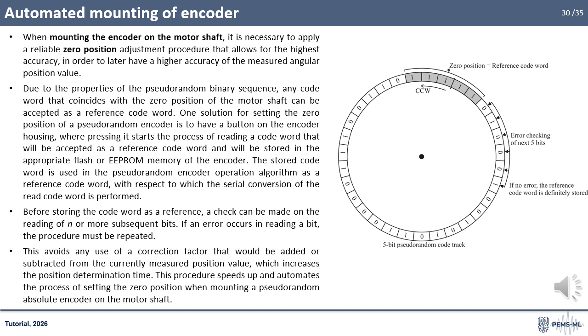One solution for setting the zero position of a pseudorandom encoder is to have a button on the encoder housing, where pressing it starts the process of reading a code word that will be accepted as a reference code word and will be stored in the appropriate flash or EEPROM memory of the encoder. The stored code word is used in the pseudorandom encoder operation algorithm as a reference code word, with respect to which the serial conversion of the read code word is performed.